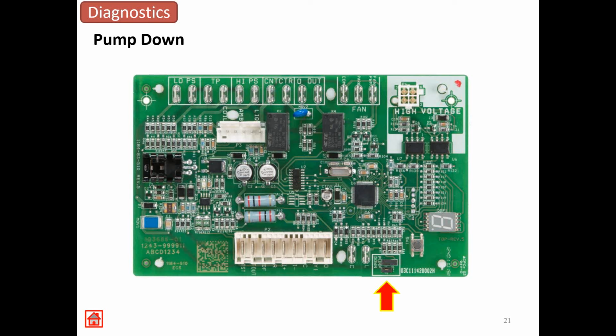But I use this more for diagnostics than what most guys think about. If we're unsure of whether or not the board is communicating, or whether or not the compressor will even run, turn the switch on, see if the thing will run. I actually did that yesterday with a customer, and we got the compressor to run. So I knew then it was not a bad compressor, and we were en route to diagnose the compressor as bad. So it's a great diagnostic tool, and I use it quite regularly.